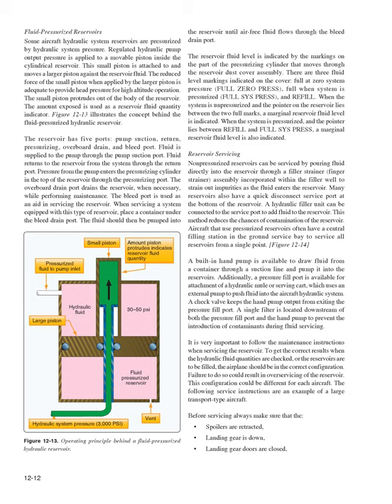Fluid is supplied to the pump through the pump suction port. Fluid returns to the reservoir from the system through the return port. Pressure from the pump enters the pressurizing cylinder in the top of the reservoir through the pressurizing port. The overboard drain port drains the reservoir, when necessary, while performing maintenance. The bleed port is used as an aid in servicing the reservoir.